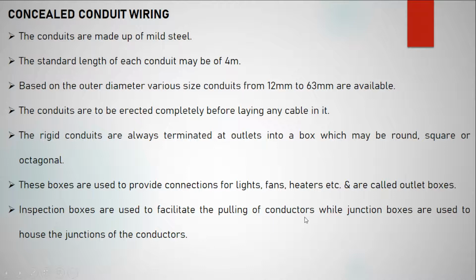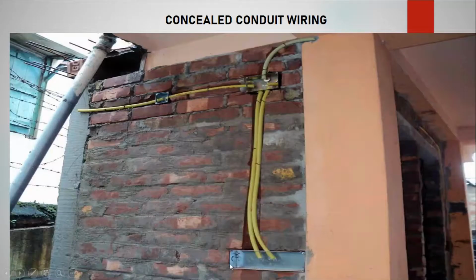Inspection boxes are used to facilitate the pulling of conductors, while junction boxes are used to house the junctions of the conductors. So there are two types of boxes: one is the inspection box, the second is the junction box. Though in some places they put inspection boxes in between just to pull the conductors. It is very difficult to run very long conductors. So what they do is provide small junction boxes in various places, cut the conduits, and once again give connections to the boxes.